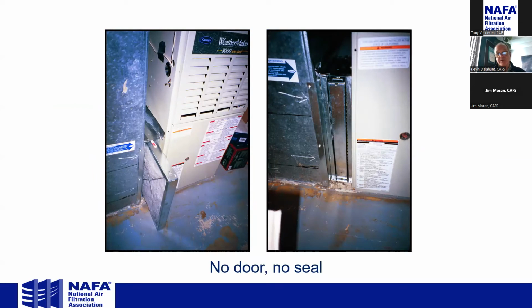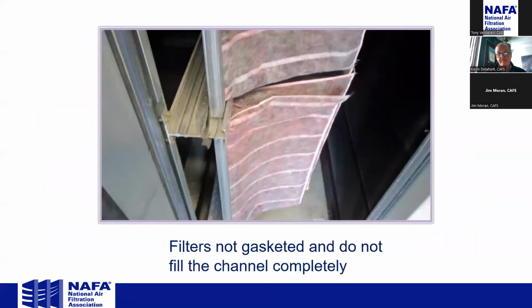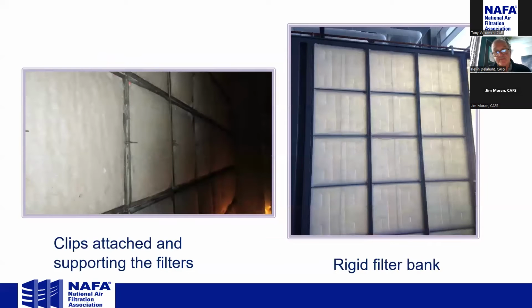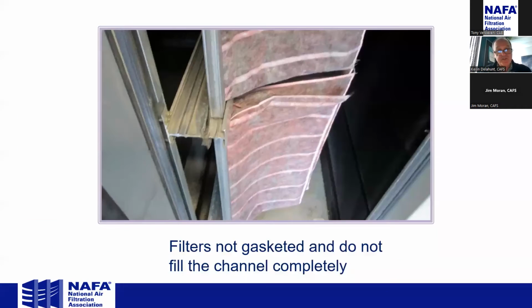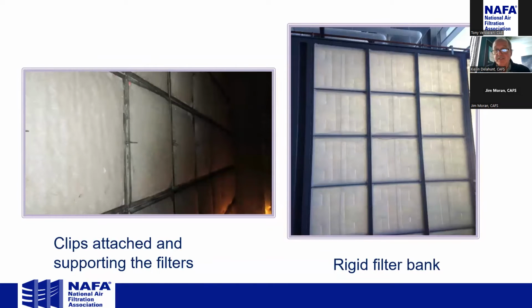In some cases, we see even a furnace with no door on it, no seal. Air is going to go around that. In this case, you see that the filters don't come completely to the end of the channel, leaving probably 1.5 to 2 inches of chance for air to bypass this filter. So no gasketing, no seal at the door. In this one, on the left and the right hand side, are two well designed and operating filter systems with the air hitting the filter perpendicular and providing a very solid seal, and hopefully increasing the overall performance of the filter bank.